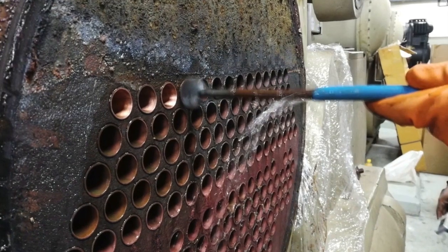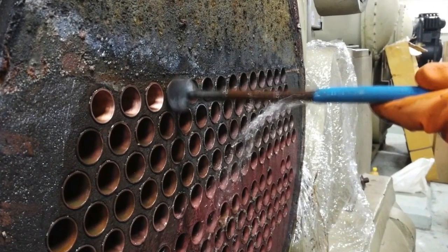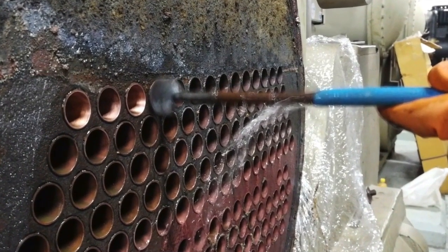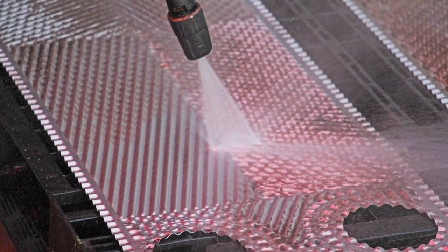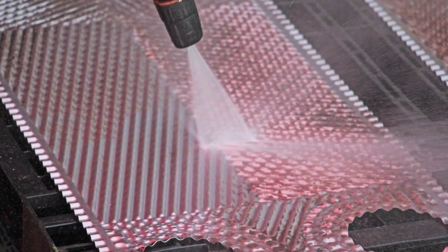When, on the other hand, the fluids involved in the exchange can be dirty, at this point we must take it into consideration. What causes dirtiness? As I was saying, it depends on the fluids. There are different types of dirt. There is a contamination at the level of encrustation when we have fluids that, so to speak, stick, adhere to the exchange walls, and I would say that this is probably the worst case. Or we have a fouling due to suspended solids circulating inside the exchanger.